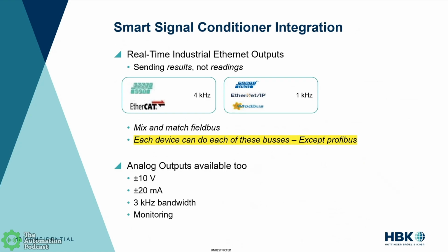I could definitely see people wanting to put this in between an existing sensor and an existing controller to get it on Ethernet IP, Profinet, EtherCAT, or Modbus TCP, whatever. By having these legacy outputs, plus or minus 10 or plus or minus 20 milliamps, you could now put that device in. I can also see people using the local panel meter for proximity viewing, but also using those outputs for IoT. There are situations where you don't want your field bus or OT network connected to the cloud because you don't want to be exposed to hackers. So this gives you a way to have an output-only connection that can go to an IoT system and give the cloud viewing capabilities without writing capabilities. That is very cool.